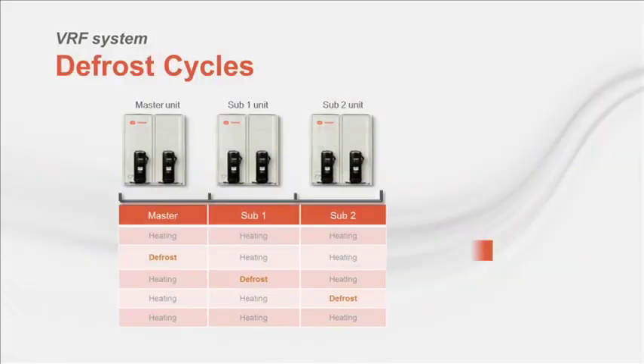A defrost cycle has a negative impact on both comfort and energy efficiency. On a VRF system with multiple outdoor units, comfort can be maintained by using a rotational defrost pattern, which means that one or two of the outdoor units continue operating in heating mode while one goes through its defrost cycle. For mini VRF or for single outdoor VRF systems, rotational defrost isn't possible. In these systems, the indoor fans are turned off to reduce comfort issues as the system switches to cooling. Comfort needs to be further considered because the time-weighted capacity of a system is reduced due to the defrost cycle.